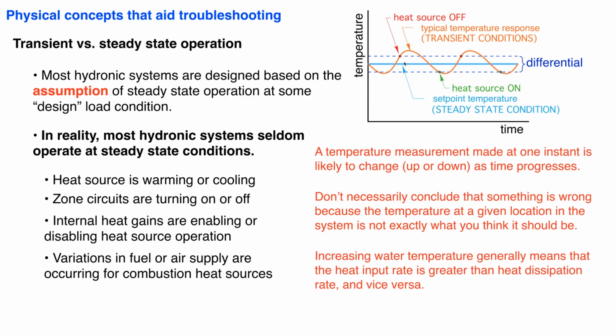But keep in mind, and this kind of goes back to thermal equilibrium, if you're watching a temperature in the system going up, it's generally because the rate of heat input is greater than the rate of heat dissipation. The system is moving towards that thermal equilibrium condition, and vice versa. If you're watching a temperature going down, even if the heat source is operating under whatever condition that system is at, something is taking heat away from that water faster than your heat source is putting heat into that water. So this does complicate troubleshooting. Troubleshooting would be a lot easier if systems always operated at some fixed steady state condition.